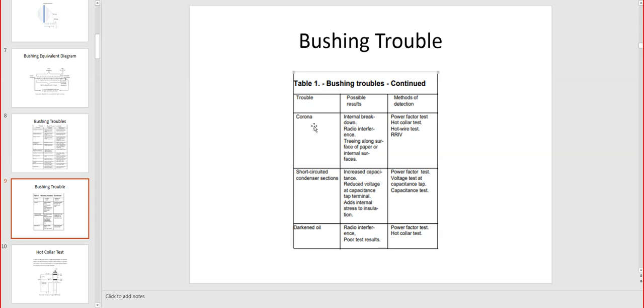And if that corona is persistent and high, it is actually an indication of damage, and it can be detected through other tests like radio frequency. We will not go there in this presentation, but there are other tests that can be done for specialized testing, like RIV, to detect if there is a permanent leakage on the surface of the bushing. Like the example I gave you with the rotten animal that got blown up on the bushing, that definitely will give you a high corona or more. So corona, if it's not addressed, will deteriorate into a bolted short. So slowly but surely it is going to take that part out and the damage will be severe.